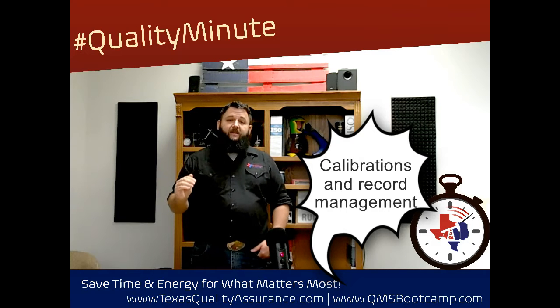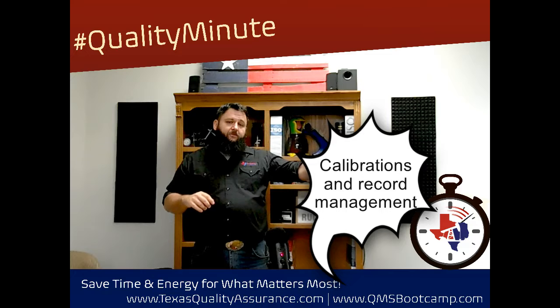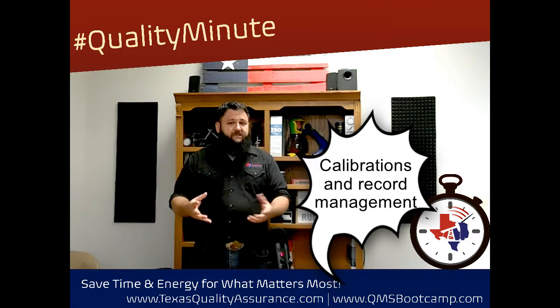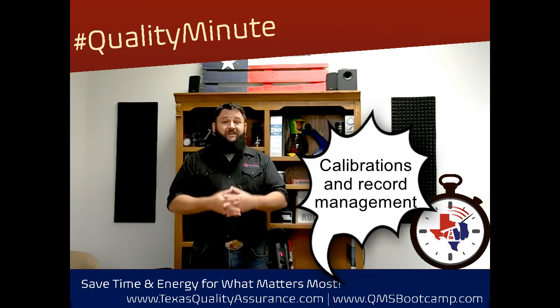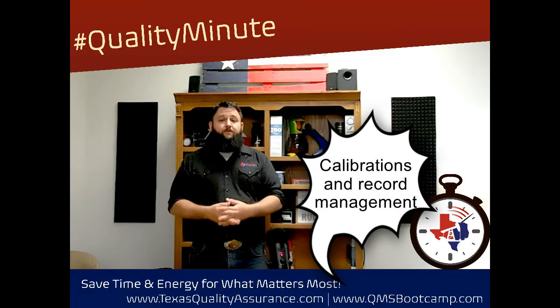So this kind of necessitates what a lot of folks do is that they create this secondary register, the secondary index of every time we had an inspection, we also note the tool that was used, and then that allows us to filter all of the inspections from the past 11 months to only the ones that were used with that tool, and then we can go cross-check those and come up with some system or some way of determining when the tool went bad. Do we need to contact a customer? What are our issues? It's really complicated, and it's oftentimes very difficult to do.